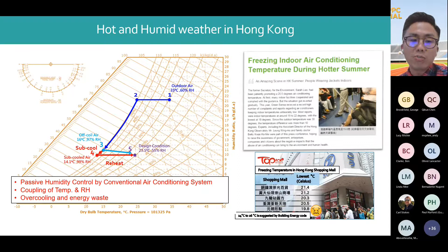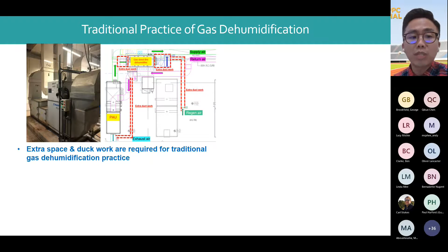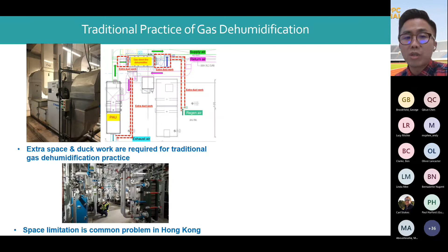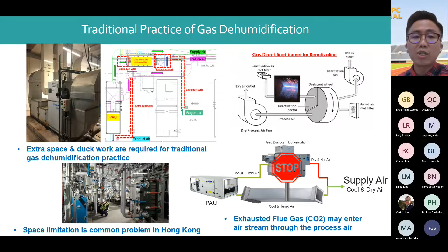Town gas desiccant dehumidification is a more energy-saving way for temperature and humidity control because it consumes less cooling energy. However, traditional practice requires extra space to install a standalone desiccant dehumidifier with additional ductwork connection to the primary air handling unit, which is very difficult to install in Hong Kong due to space limitations. Another problem is that flue gas from the direct fire burner may enter the airstream through the processed air because the dehumidifier is not 100% air sealed, which may raise safety concerns from clients. My project is to provide a comprehensive solution for those problems and also to integrate new features to increase the competitiveness of dehumidification by gas energy in the market.